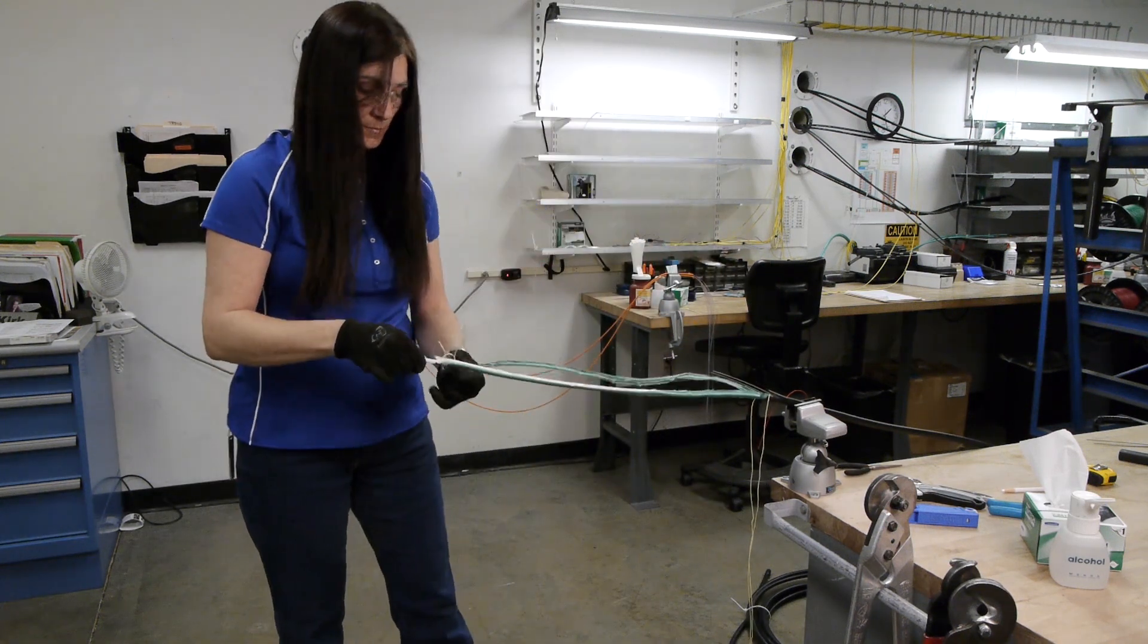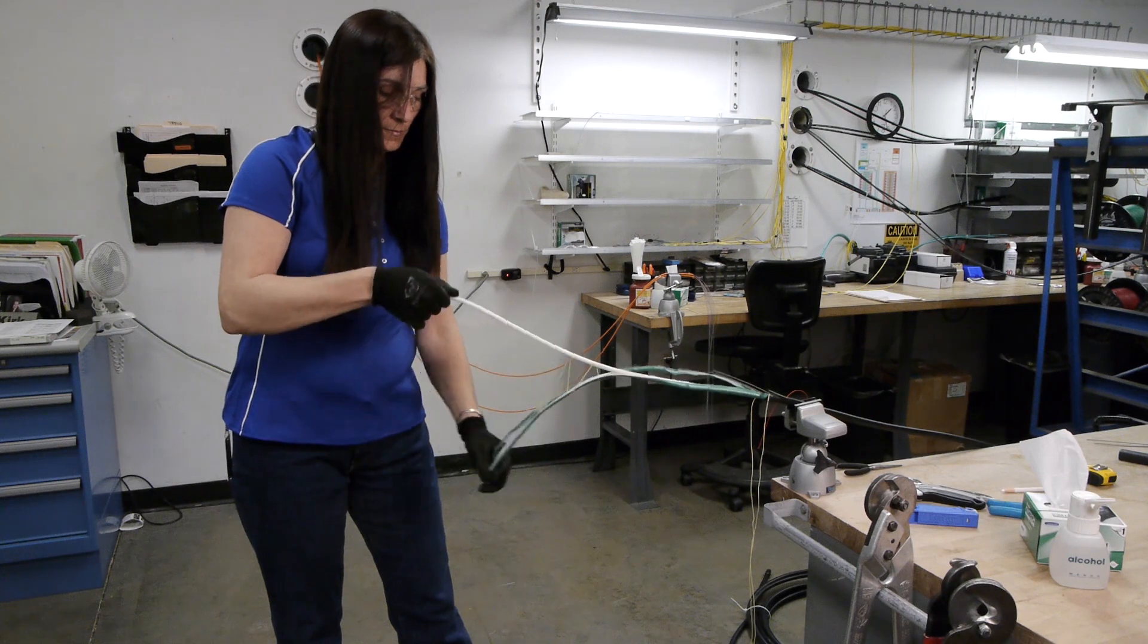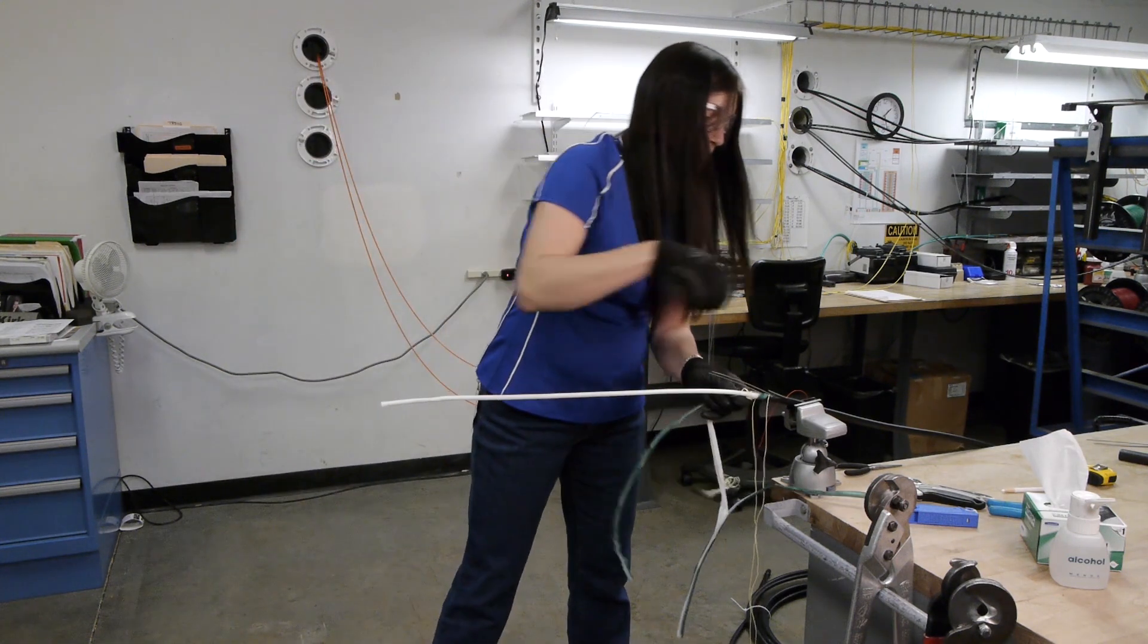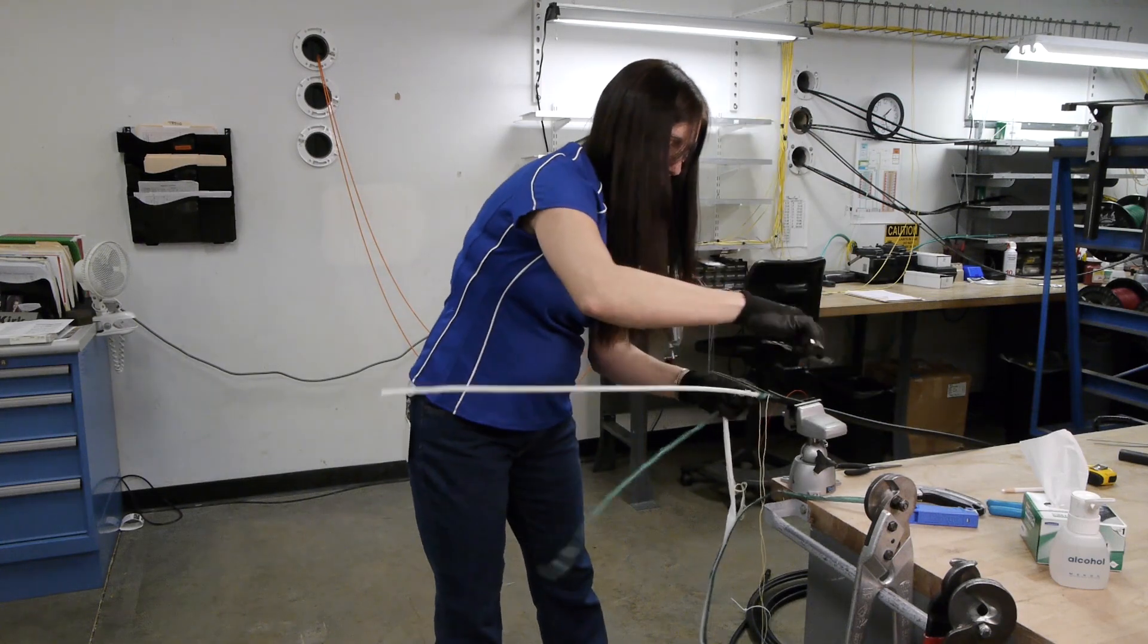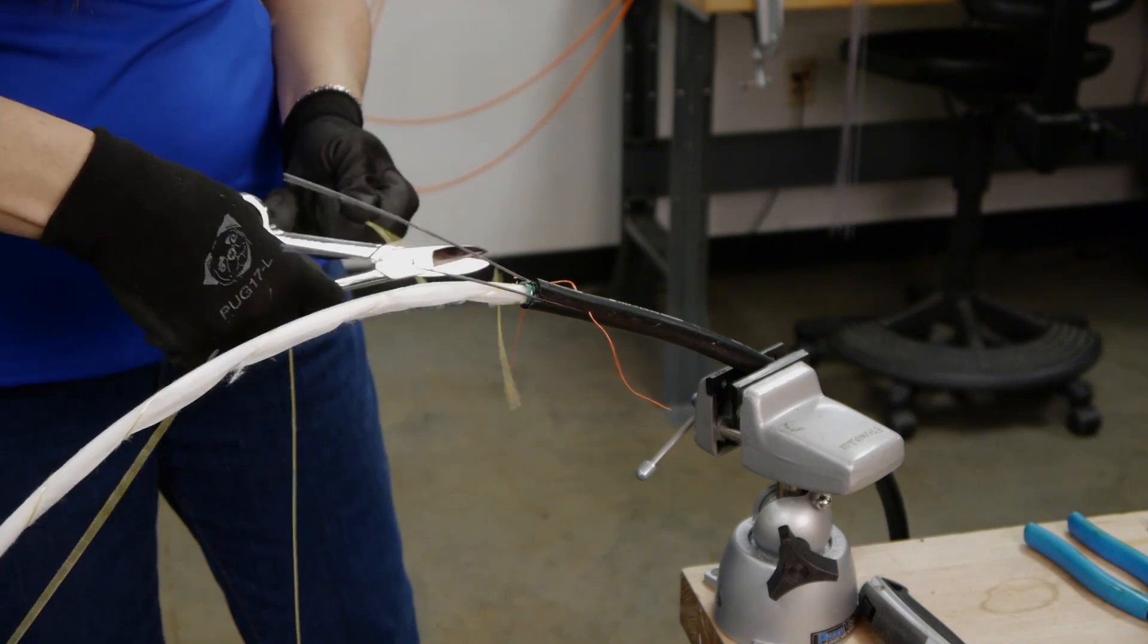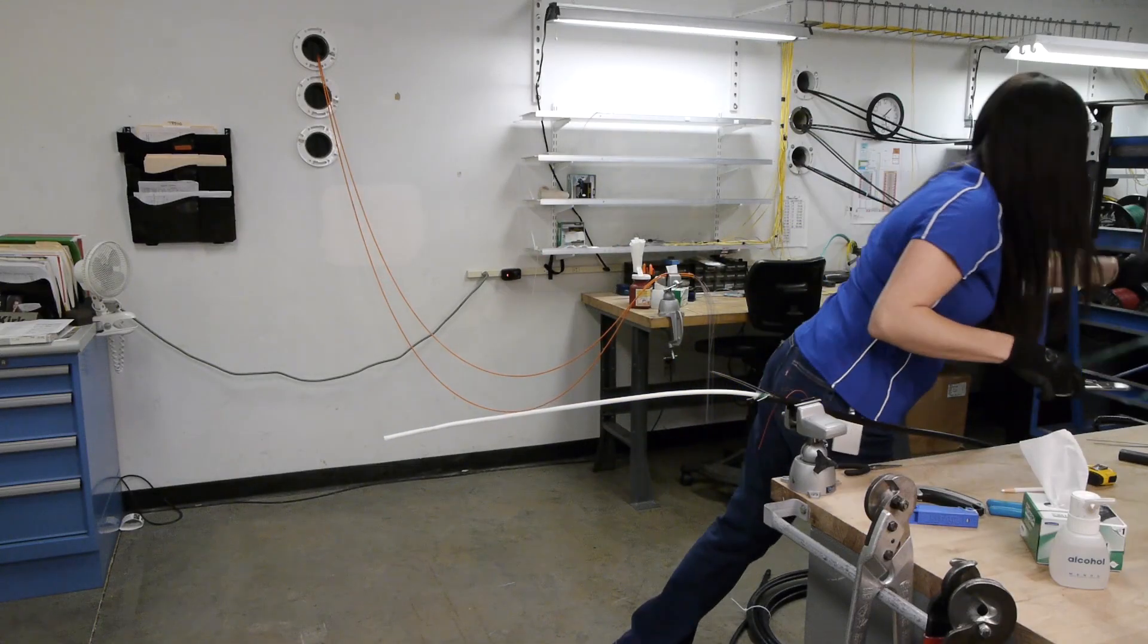Remove armor and cut off dry water blocking yarns and material. Cut and leave several inches of rip cord for bond clamp installation.